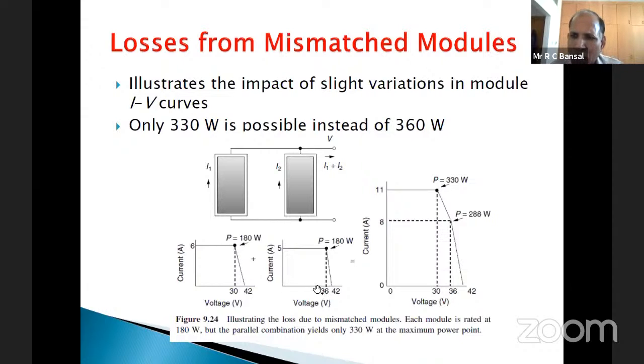We may think we need an extension of 180 watt panels and can simply add modules from a different manufacturer, assuming that since the power rating is the same, it will serve the purpose. But if the voltage and current ratings differ, that's what we call mismatch of the module. So when we connect these two modules, each 180 watts but with different voltage and current ratings...